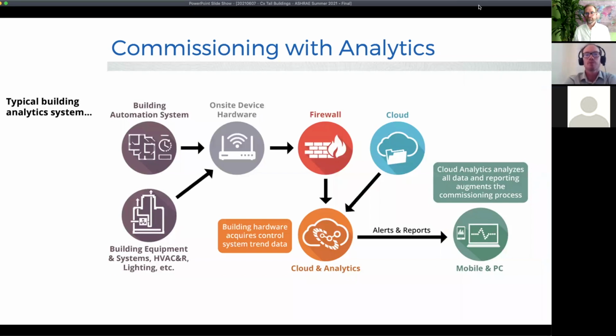Okay, so if we're looking at either BAS or BMS trending, we should have the discussion about using that data. If it's not strictly alarm-based, or we're not doing something on the graphics side, this is a perfectly sound and reasonable tool in the toolbox that we, the building owner, operations, or whomever can use—and that would be analytics. I'm definitely a fan of using analytics; there's a ton of capability and insight that can be generated.